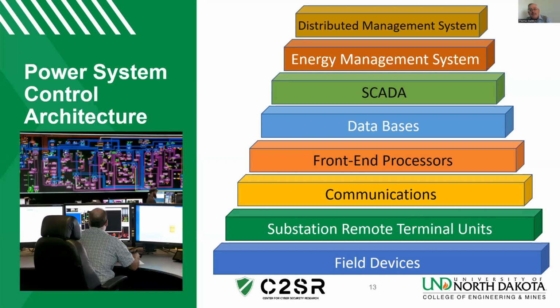If we look at it from a structural standpoint, we have a number of different systems going on. At the utility level, we have the distribution management system, similar to the control center for the transmission level, the energy management system for transmission with SCADA, databases collecting the various pieces of data, historical data as well as current data, our front-end processors collecting data from the field, the communications back and forth of control signals as well as sensor signals, and our substation remote terminal units that interface to the various relays and controls for our transformers and capacitor banks, and hence all the field devices throughout the substations that provide this service for us.